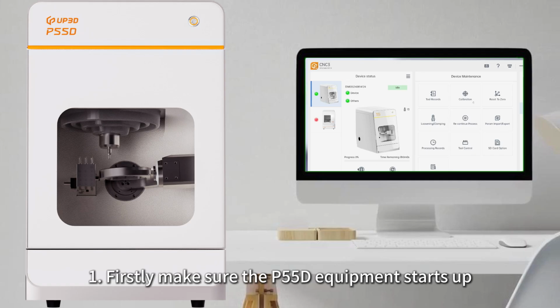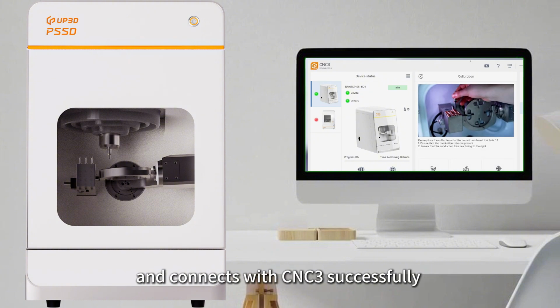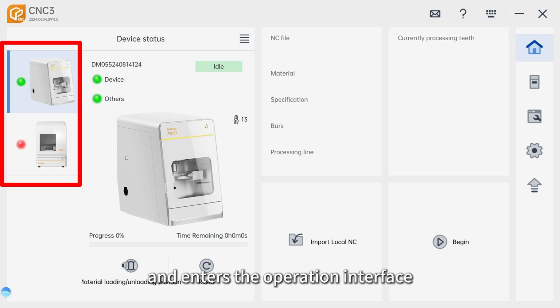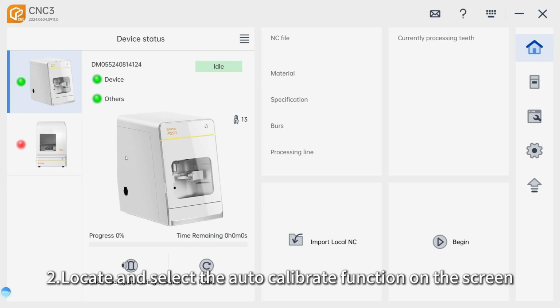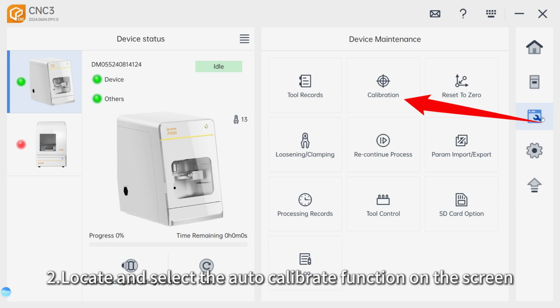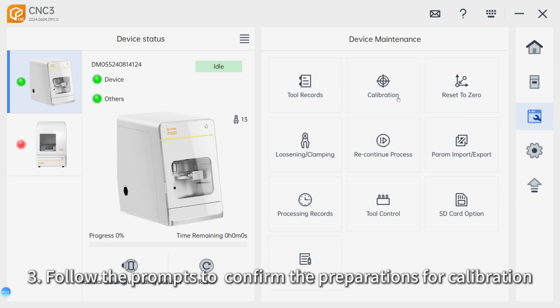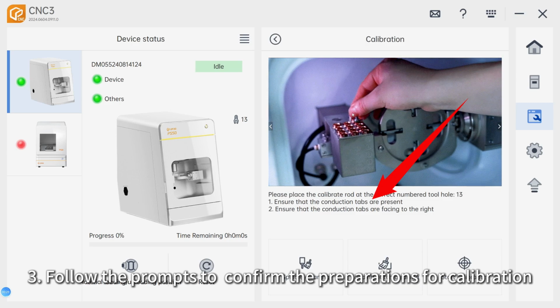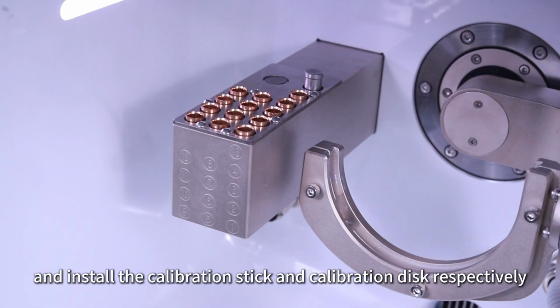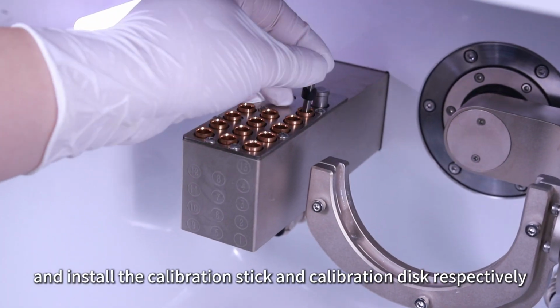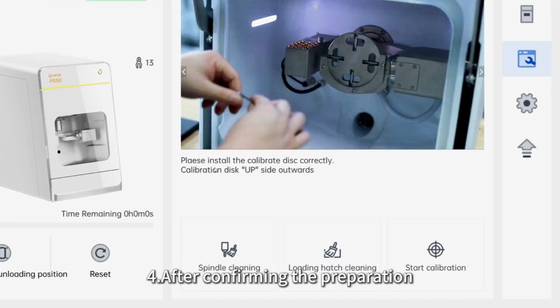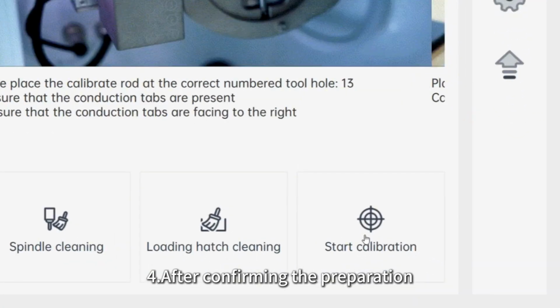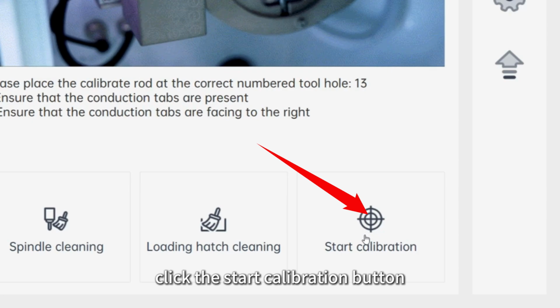1. Firstly, make sure the P55D equipment starts up and connects with CNC3 successfully and enters the operation interface. 2. Locate and select the auto-calibrate function on the screen. 3. Follow the prompts to confirm the preparations for calibration and install the calibration stick and calibration disc respectively. 4. After confirming the preparation, click the Start Calibration button.